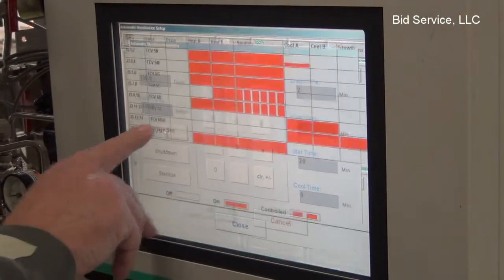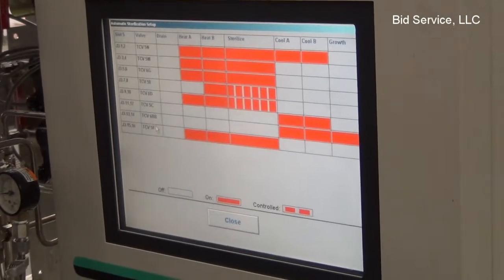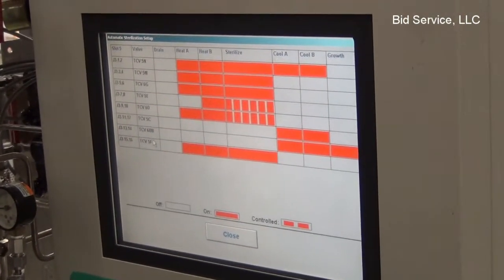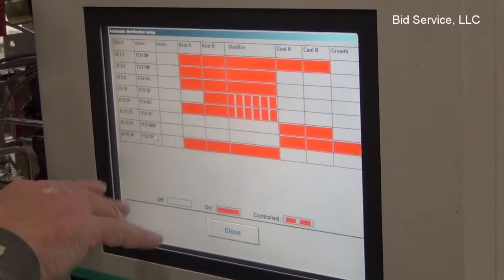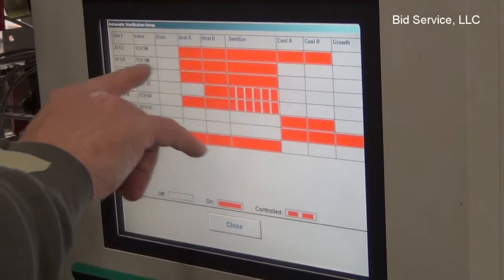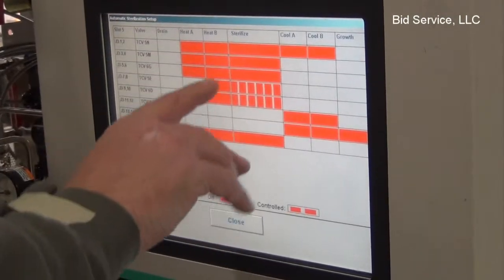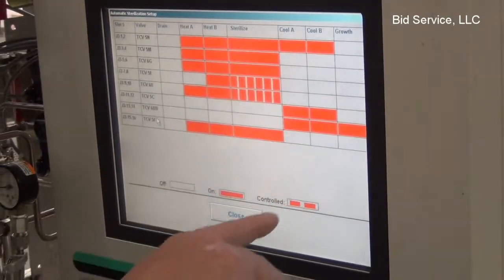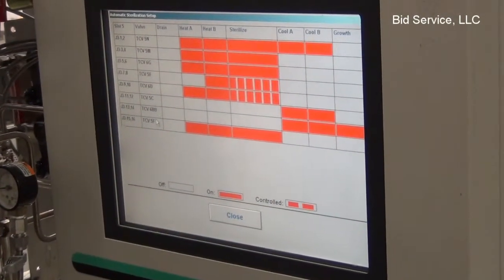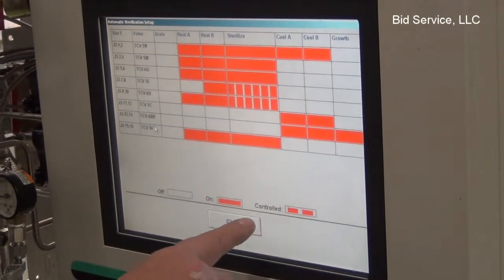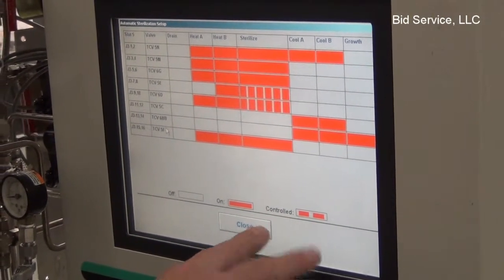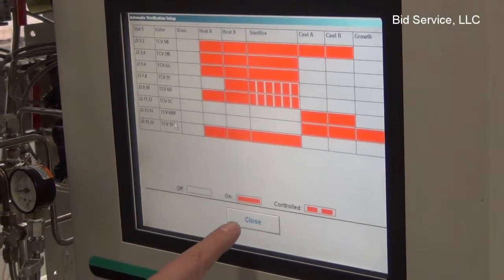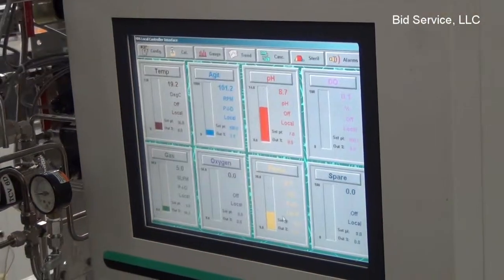A handy thing to see is the valve sequencing. If you're in the sterilization program, it shows you all the slots and the valves that are involved. It's still running. Heating A, heating B, sterilizing, cooling A, cooling B. And it shows you off, on, controlled, which would be pulsed, basically.